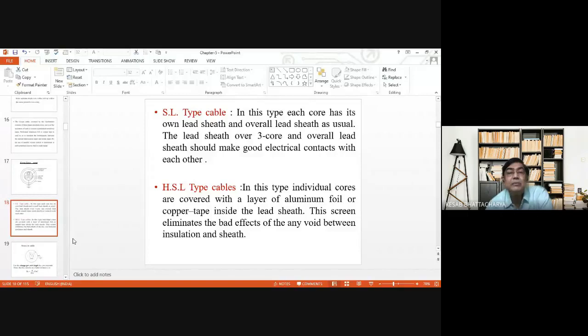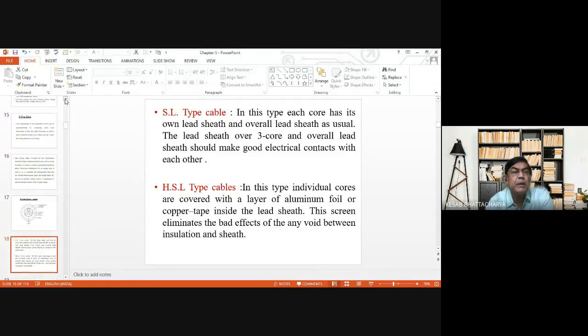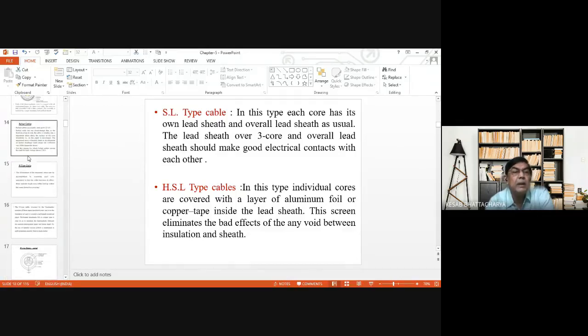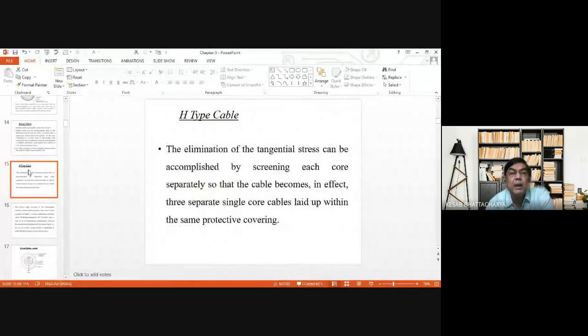These are basically, for example, SL type cable or H type cable. If we consider H type of cable: the elimination of tangential stress can be accomplished by screening each core separately, so that the cable becomes, in effect, three separate single core cables laid up within the same protective covering.